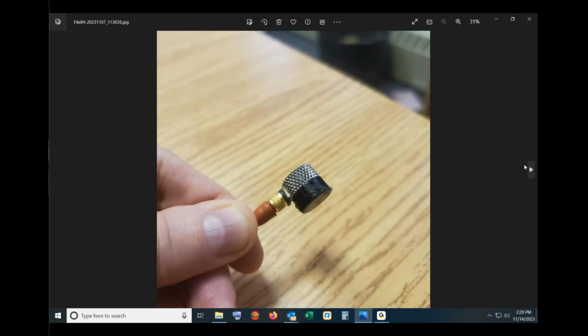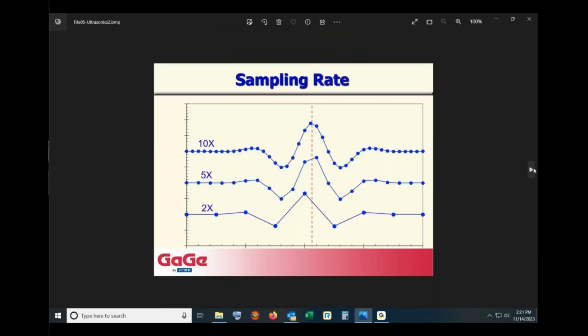Here's the ultrasonic transducer I'm using. It's a contact ultrasonic transducer. The one in the image I showed you was made to be immersed in water, which you often do, but in this case, we'll be applying the ultrasonic transducer directly to the material under study. The first thing I'm going to show you is the advantage of sampling rate.